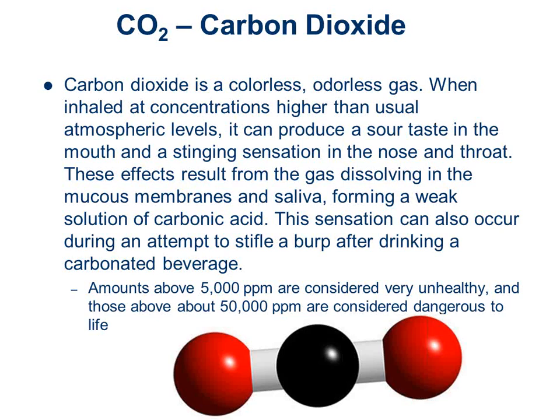So the reason we monitor CO2 is not because of a safety issue. The reason we monitor CO2 is as a surrogate to count the number of people breathing in a room. And if I know how many of you are in there breathing, I can decide how much ventilation air I need to bring in for safety and code and all that good stuff. So we'll talk more about that application as we go. But CO2 is an extremely common gas monitored, and perhaps arguably in commercial buildings, the most common thing that we would have sensors for.